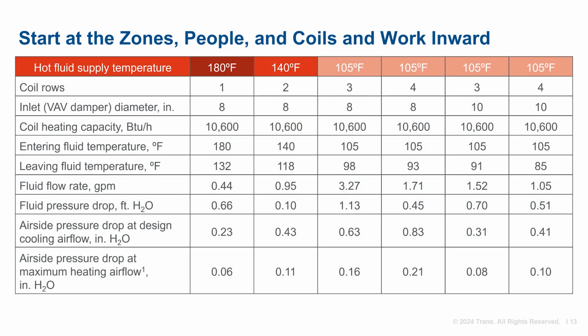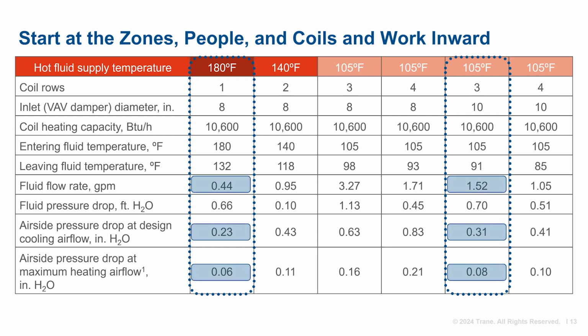This diagram and table is from the engineer's newsletter, Heating with Lower Temperature Hot Water, which goes through trade-offs in more detail with real product data. One scenario, a single row coil selected for 180 degrees Fahrenheit with about a 50-degree delta T in the far left column, could be replaced by several different coils of the same capacity and still result in the same leaving air temperature and volume. The second to last column is a 3-row coil in a larger box, moving from an 8 to a 10-inch inlet damper diameter. For the same capacity, higher flow is required at similar air and water side pressure drops. If there's space, this might be a good trade-off for reducing hot fluid temperatures.